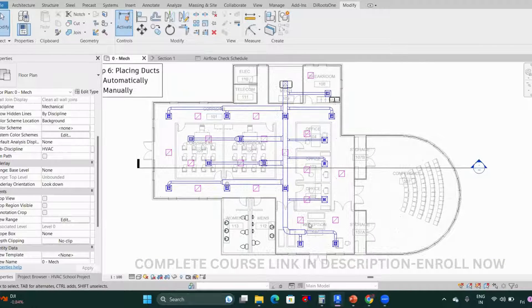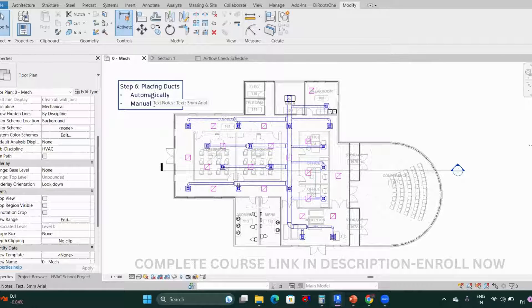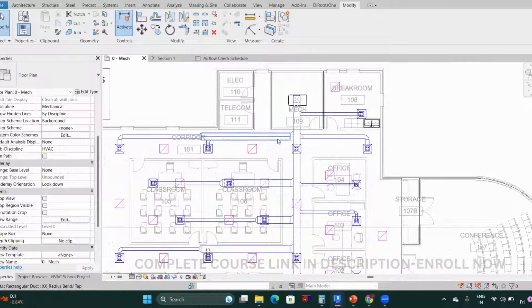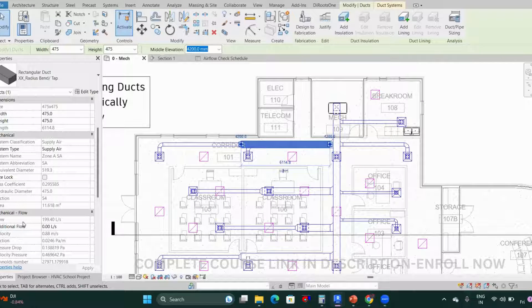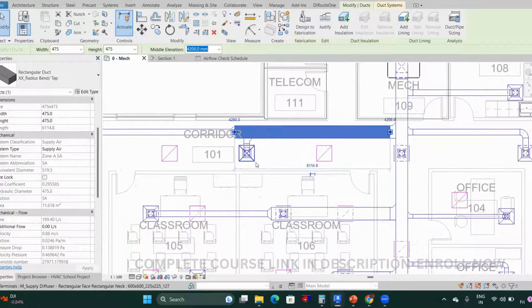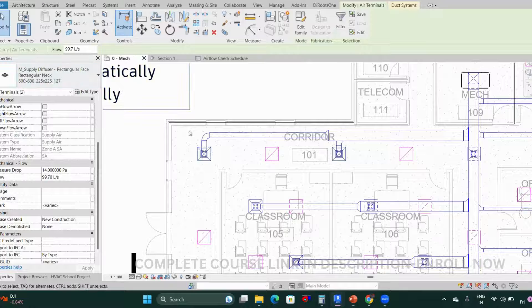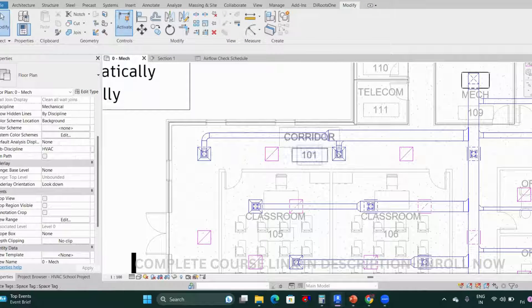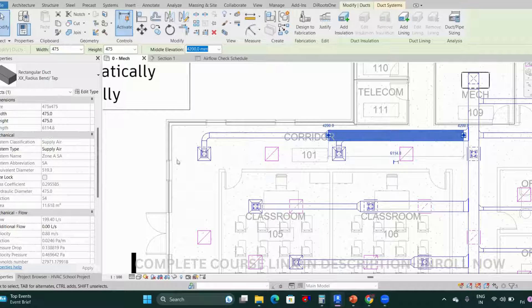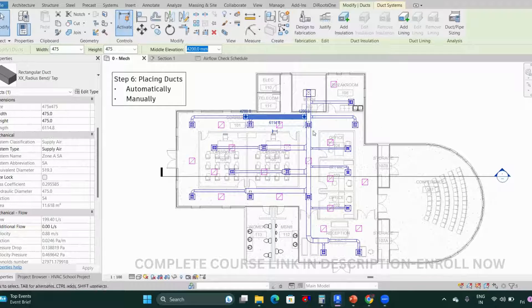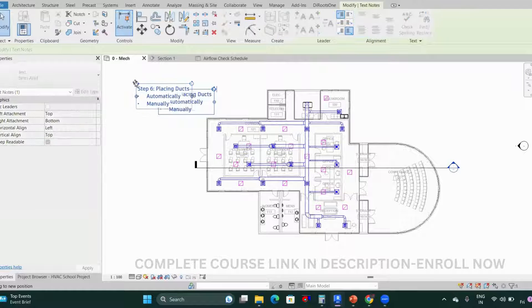Okay, there is a small connection issue but mostly it's fine. Your layout is ready, but note that the ducts are not yet sized — this is just the placement. When you check the ducts, you'll see flow rates: for example, 199 CFM, because 99.7 plus 99.7 equals approximately 199 total flow in the duct.